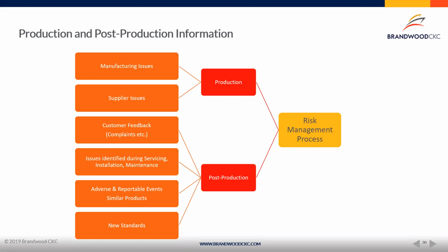From a post-production side, these are all the things that, once the device is in the hands of the end users or in the intended use environment, give you additional considerations around the risk. Customer feedback is the obvious one.